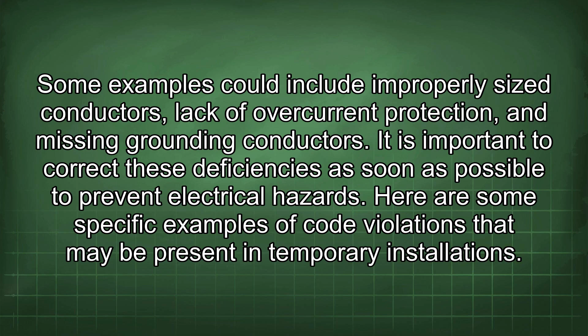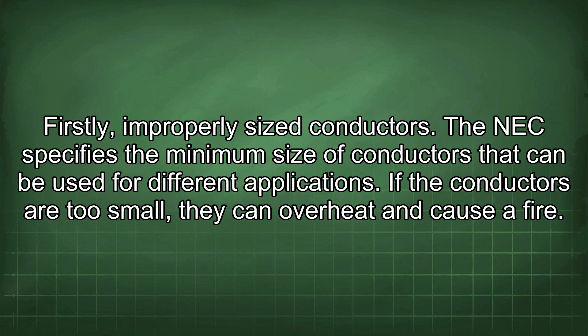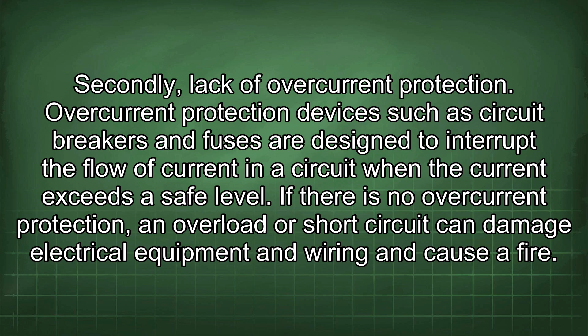Here are some specific examples of code violations that may be present in temporary installations. Firstly, improperly sized conductors. The NEC specifies the minimum size of conductors that can be used for different applications. If the conductors are too small, they can overheat and cause a fire. Secondly, lack of overcurrent protection. Overcurrent protection devices such as circuit breakers and fuses are designed to interrupt the flow of current in a circuit when the current exceeds a safe level. If there is no overcurrent protection, an overload or short circuit can damage electrical equipment and wiring and cause a fire.